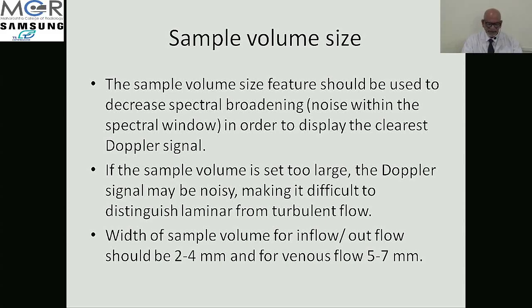If the sample volume is set too large, for example 8 or 10 mm instead of 4 or 5 mm, the Doppler signals may be noisy, making it difficult to distinguish laminar from turbulent flow. The whole envelope will be filled with velocities and it will lose its importance as a pulsed-wave sample volume.